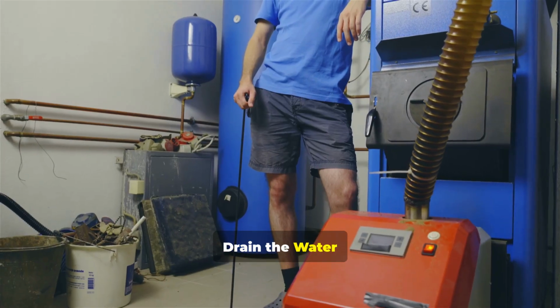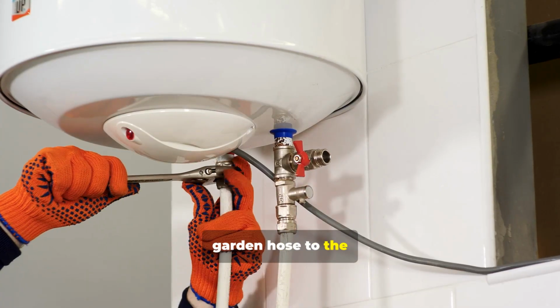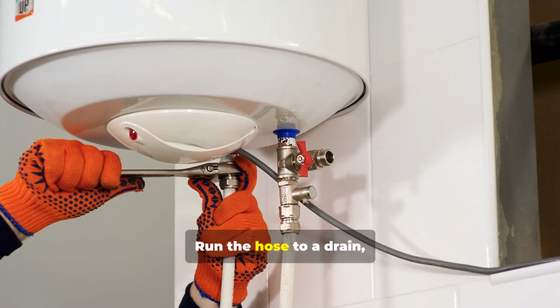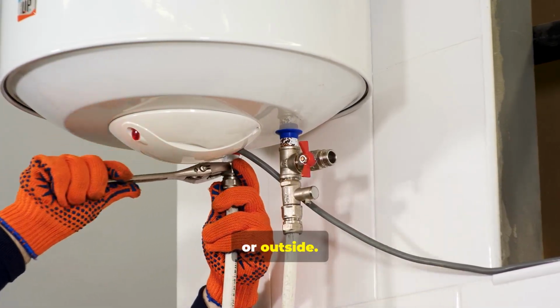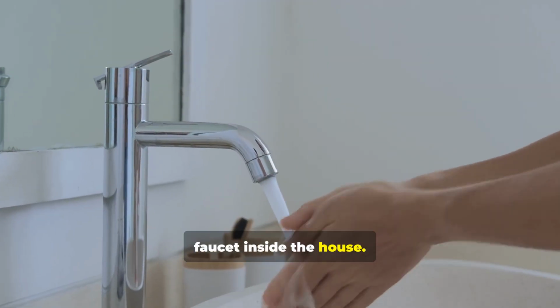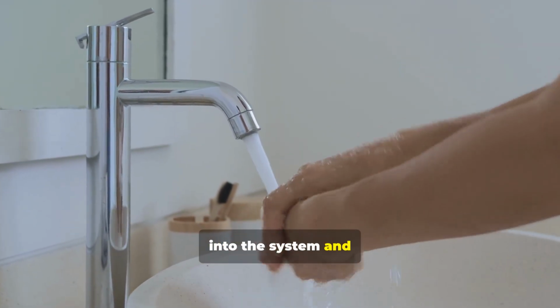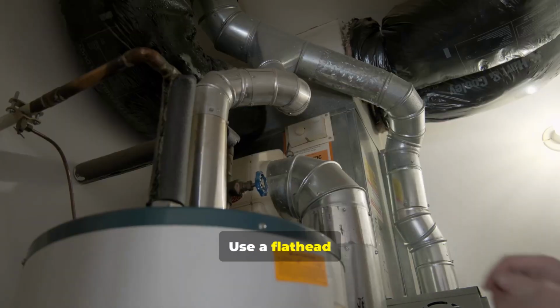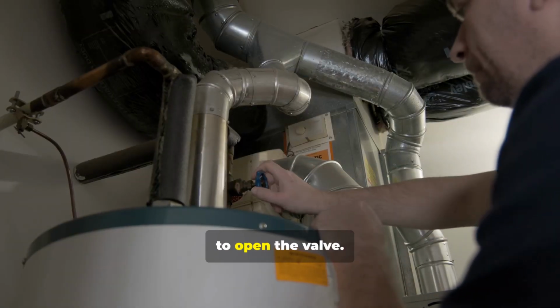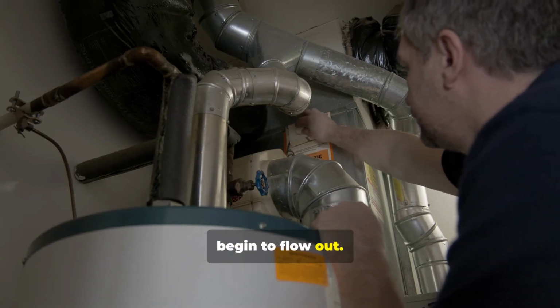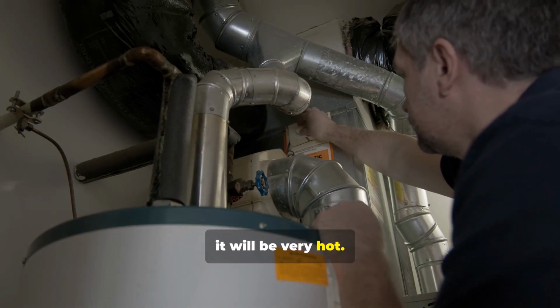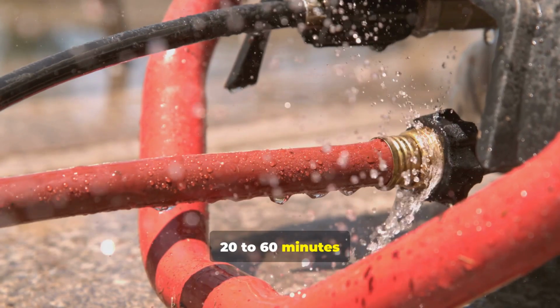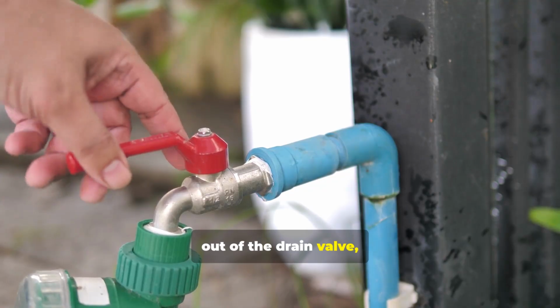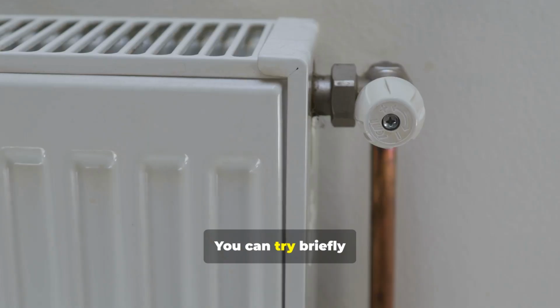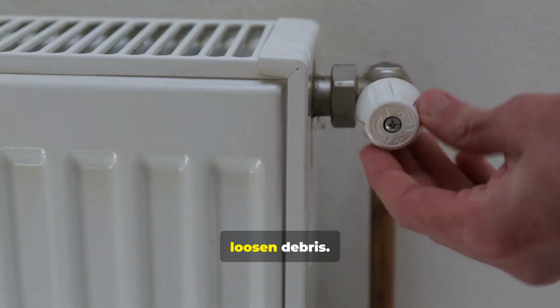Step 2. Drain the water heater. Connect a garden hose to the drain valve at the bottom of the tank. Run the hose to a drain, sump pump, or outside. Open a hot water faucet inside the house. This allows air into the system and helps the tank drain faster. Use a flathead screwdriver or the drain valve handle to open the valve. The water will begin to flow out. Be cautious because it will be very hot. Draining may take 20 to 60 minutes depending on the tank size and how much sediment has built up. If nothing comes out of the drain valve, it is probably clogged with sediment. You can try briefly turning the cold water back on to loosen debris.